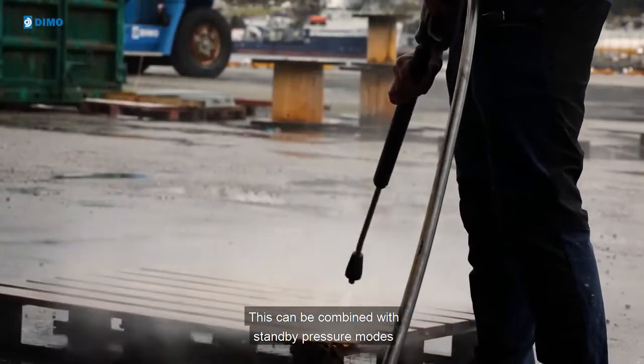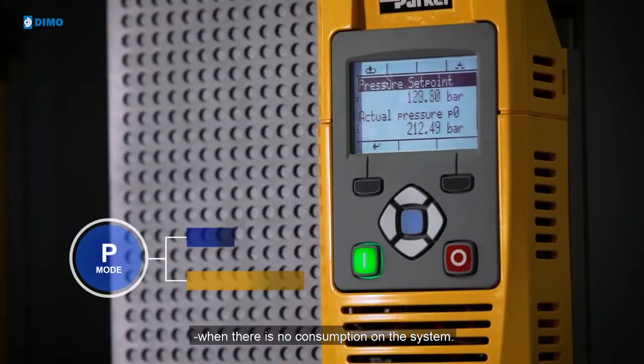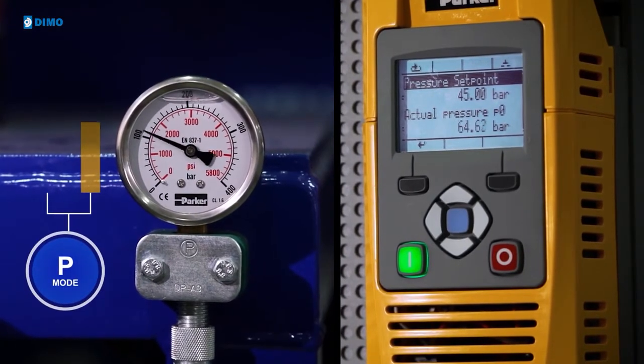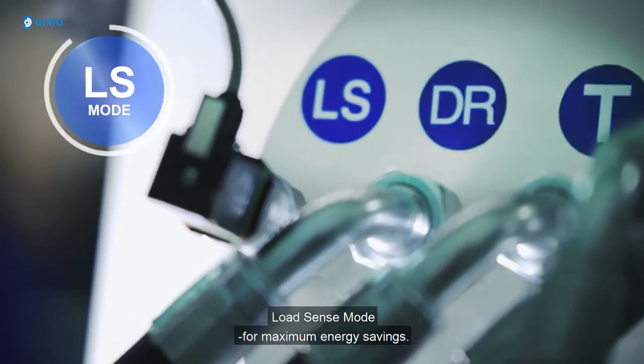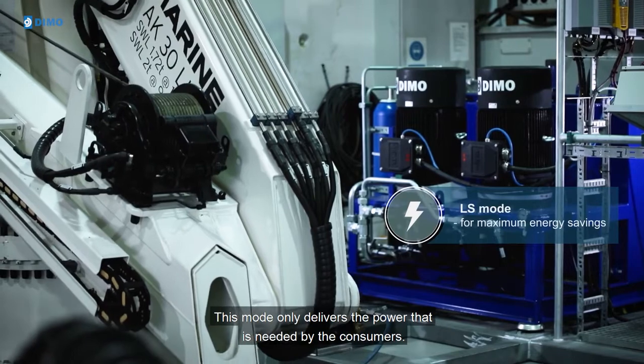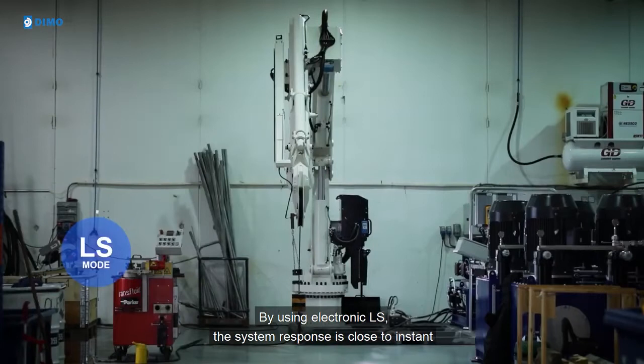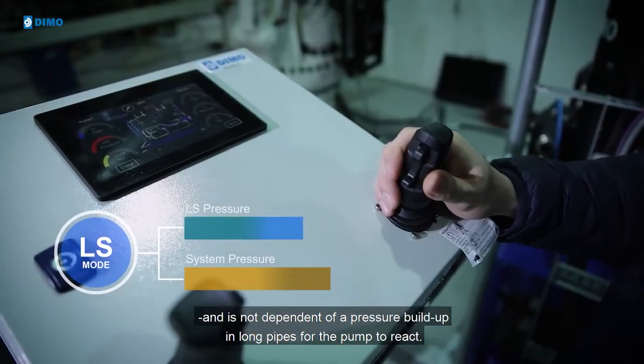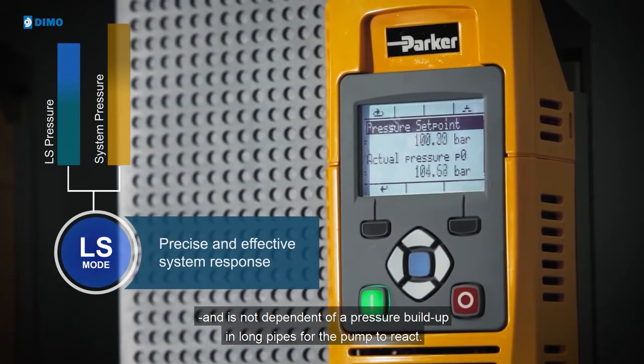This can be combined with standby pressure modes where the system pressure is reduced to a minimum when there is no consumption on the system. Load sense mode delivers maximum energy savings, providing only the power needed by the consumers. By using electronic LS, the system response is close to instant, and is not dependent on pressure buildup in long pipes for the pump to react.